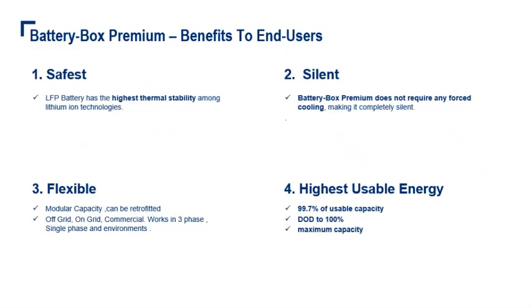Touching on the last point, highest usable energy. Residential customers may not know the difference between nominal energy and usable energy, so they might ask, hey, I've got a 14 kilowatt hour battery, but why am I only using 13.2? There's no confusion with BYD, but obviously there is a threshold in every battery below which you can't extract more power, and that's the reserve capacity. BYD gives you the option to set that limit - you can even put it at 0%, though that's not as safe. There's an option for BYD, whereas other manufacturers don't have that option.